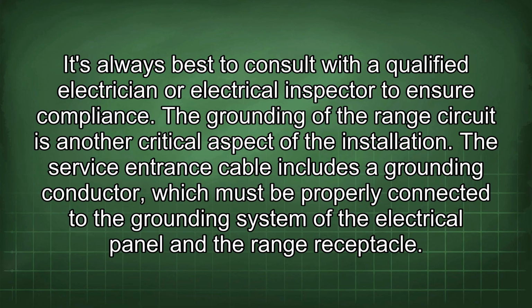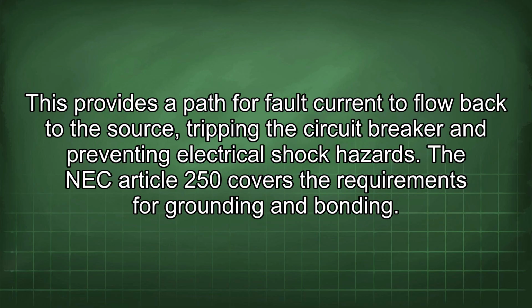The grounding of the range circuit is another critical aspect of the installation. The service entrance cable includes a grounding conductor, which must be properly connected to the grounding system of the electrical panel and the range receptacle. This provides a path for fault current to flow back to the source, tripping the circuit breaker and preventing electrical shock hazards. NEC Article 250 covers the requirements for grounding and bonding.